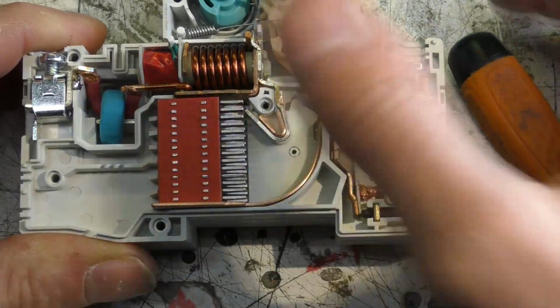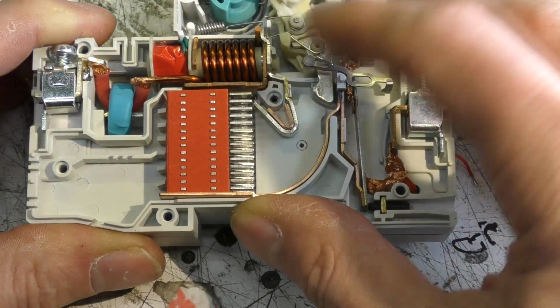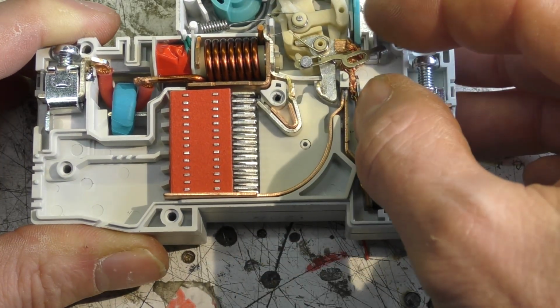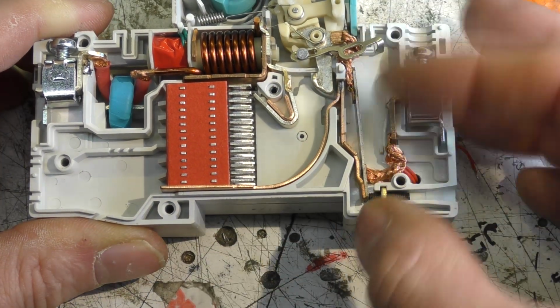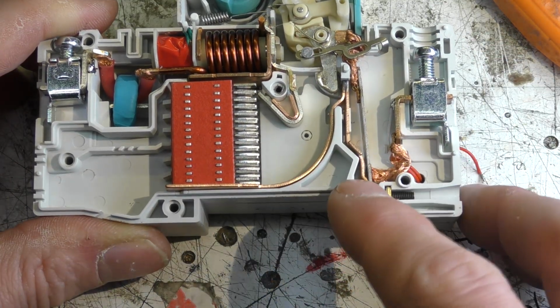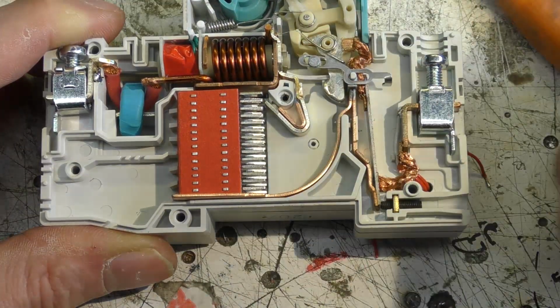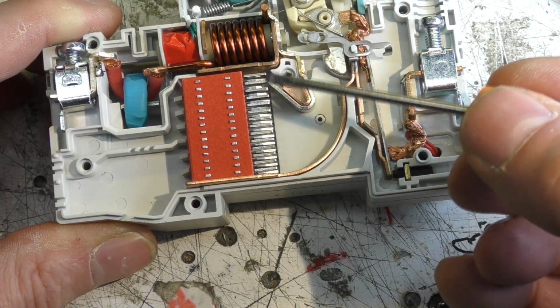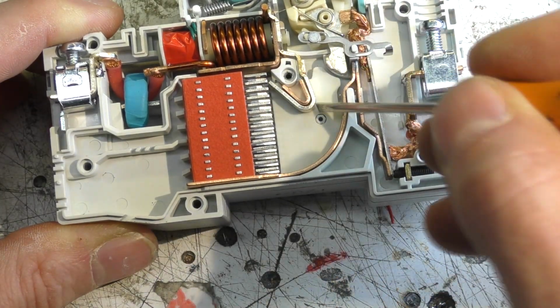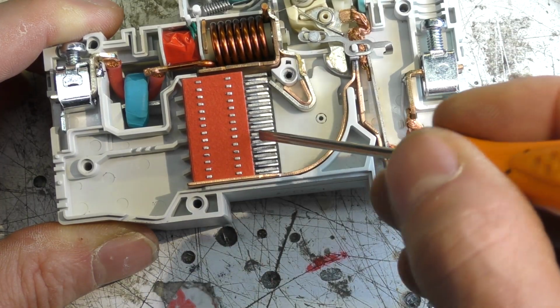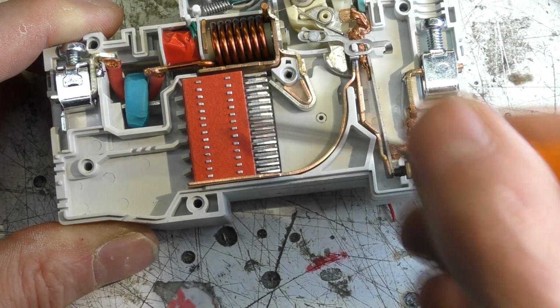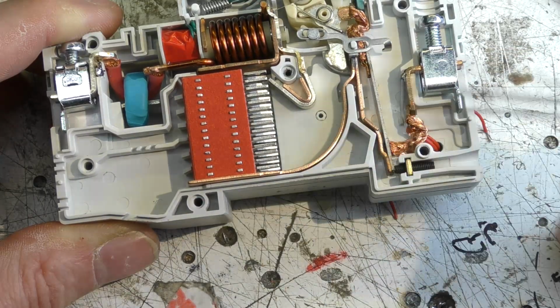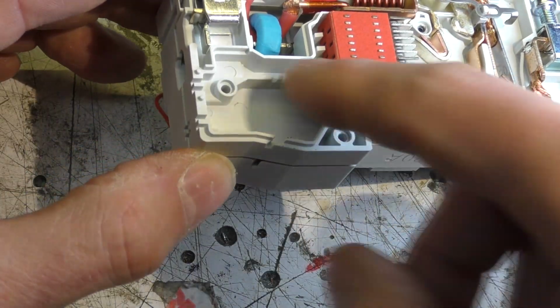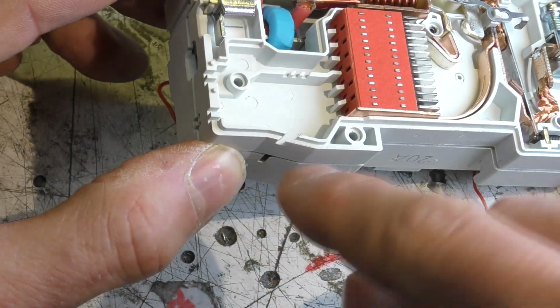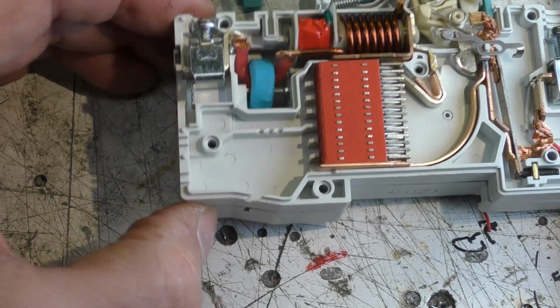Not sure what the rating this will be. May well be this is the nominal 20 amp rating of the breaker here, because the thermal trip obviously will take several seconds on a minor overload, but I'm surprised we didn't manage to trip this when sticking 50 amps through it. The overcurrent protection at least does look fairly conventional, and this is the arc path. When this opens, the arc is guided through here to these plates where it will split up into multiple arcs, and then the large area of metal will cool it down to quench it. And then just a vent at the bottom so that any rapid expansion of gases vents out of these ports here rather than making the whole thing explode.